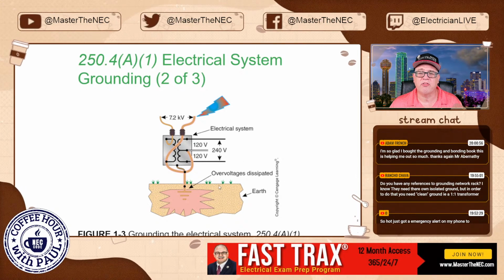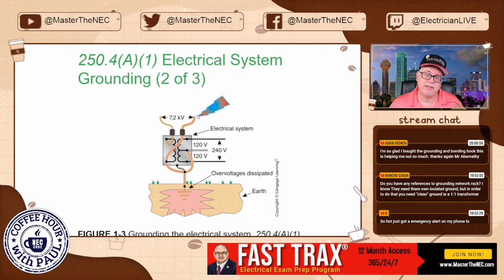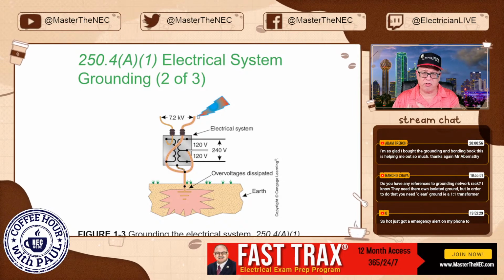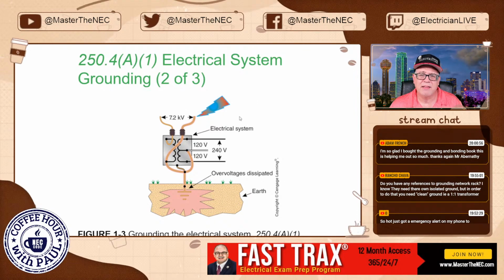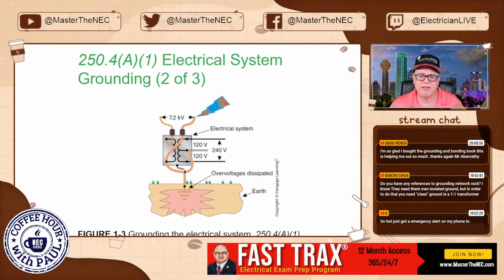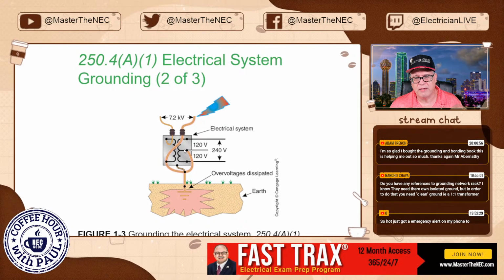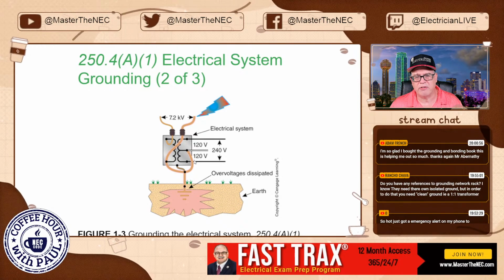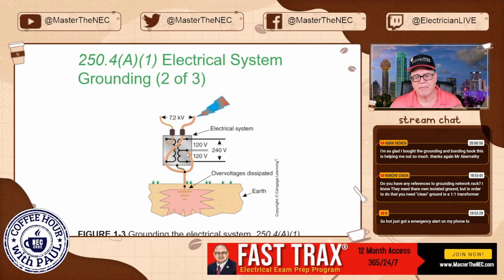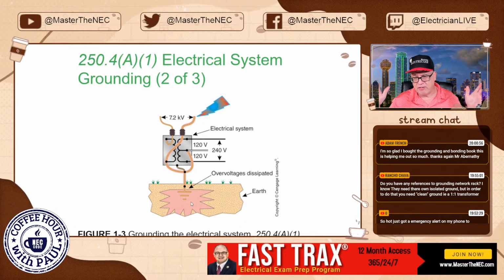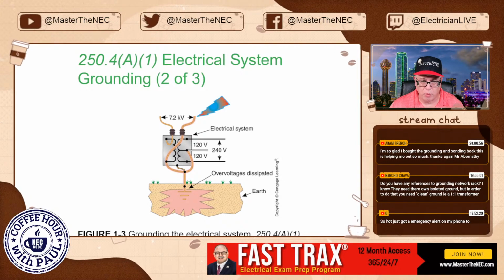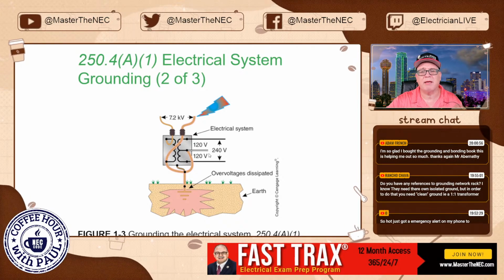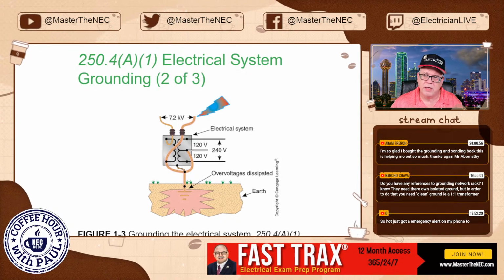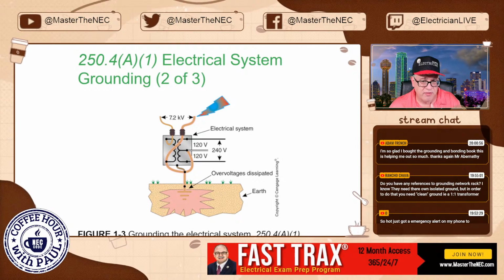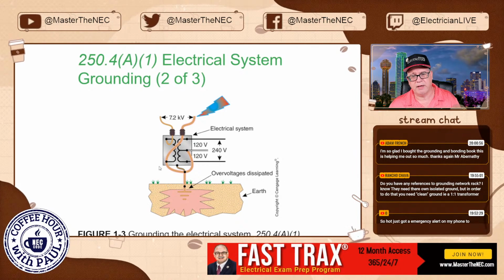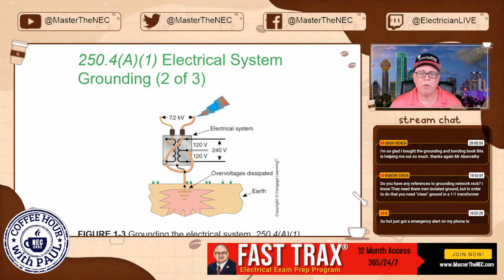Here you see if you have an overvoltage, whether it's a surge, lightning, whatever it might be, it comes here and dissipates itself to the earth. This right here would be a system bonding jumper. It gets down to earth and gets to where it needs to be, and everything's happy. We don't have anything imposed into our electrical system that's going to be risky to us if this is all done correctly. That's what we're trying to achieve here.